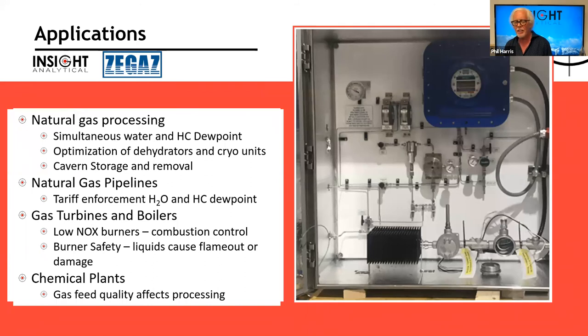So from an applications perspective, common applications are natural gas processing. Simultaneous water and hydrocarbon dew points in pipeline gases allows us to do optimization of dehydration units and cryoseparators. So if we're running a cryogenic plant, a plant where we're cooling the gas down to try to separate out natural gas liquids, it lets us see, are we actually getting to the dew point we think we're getting? If we put natural gas into caverns for storage, we have a client who, when the pipeline has more capacity than people are using, pumps all the gas into an underground cavern. And then when they need more gas, it can release gas from the cavern. Well, when it's down in the cavern, potentially it's picking up water. So now they want to know dew points.